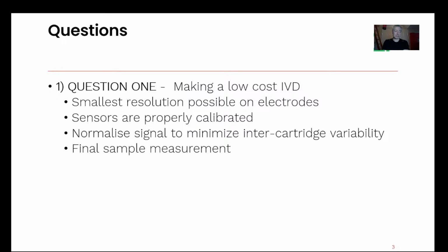And final sample measurement. We're actually doing tests on sensors where the test volumes in actual products are more like 1 microliter or 4 microliters. But just understand that most of the academic literature on electrochemistry is really imagining an infinite reservoir. So in fact, you will have, I don't want to call them problems, I want to call them interesting challenges when you try to reduce the volume. But typically a glucose sensor is working with a volume of 300 nanoliters. Zimmer and Peacock, just historical, we're often working in microfluidic devices where the volume being tested is 1 or 4 microliters. Especially if you're doing molecular assays, it's probably a good idea to reduce the sample volume because you reduce the cost of expensive materials. Anyway, I'll get to those questions as I go through today.